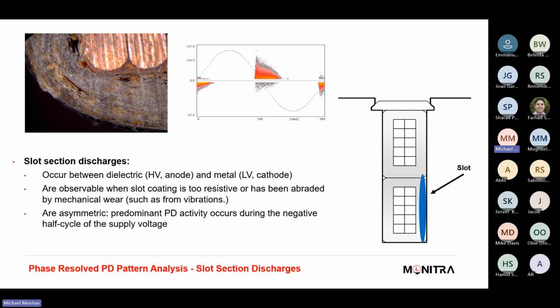And then you've got the magnitude. So the left-hand side scale there is nanocoulombs. So that's energy. So obviously the larger the energy release, potentially the larger the void, which means potentially the bigger the issue could be. So when you get 10 nano to 20 nano, which would be fairly significant PD activity, and you start to get that heat map rise where you're getting severe pulse counts, your type of diagnosis there would be, there could be severe slot discharge or voids, and they could be fairly well advanced because of the energy that's being released. And this is the way that we start to look at PD patterns and how we can try to interpret them. And I'll get on to how we can use machine learning to make this whole process a little bit easier from a very quick level.